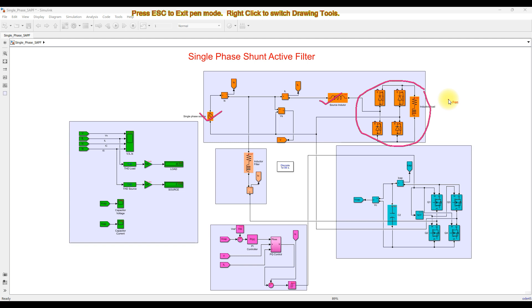Because of this nonlinear load, it will affect the nature of the source current. Normally the source current will be sinusoidal, but when we connect a nonlinear load to the system, the source current becomes non-sinusoidal. Because of this, harmonics in the source current increase and the source supplies more reactive power. When we connect some other load, it will also be affected by this nonlinear load, so we need to avoid that problem.